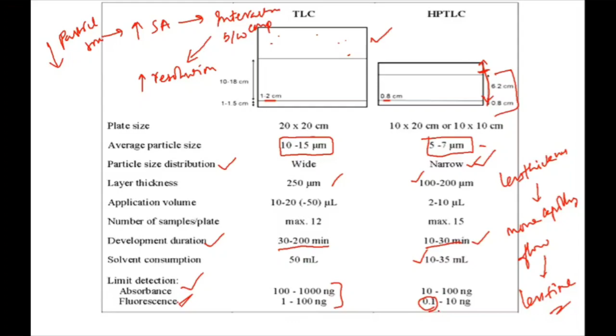The next one is detection. By using absorbance or fluorescence, the detection in case of TLC is in the 100 to 1000 nanograms range, that is 0.1 to 1 microgram. Whereas in case of HPTLC, we can go by simply choosing an appropriate detection system. If you have a fluorescence detection system, you can go up to the 0.1 nanogram level for detection of any sample.